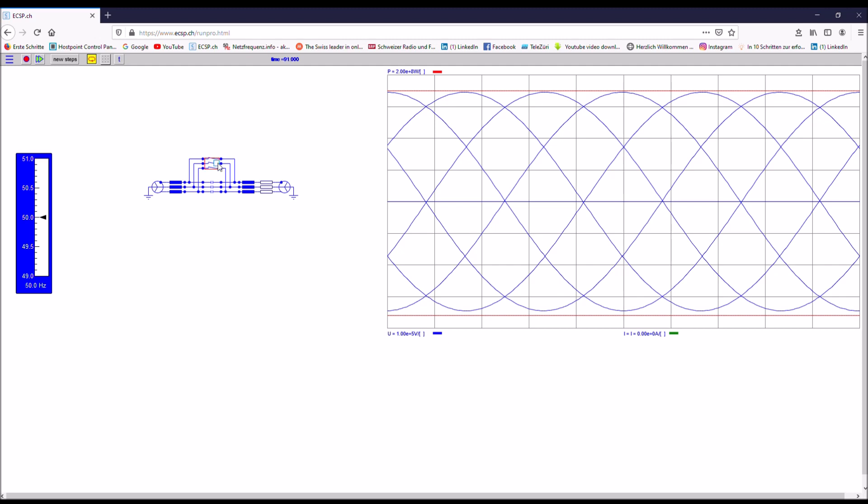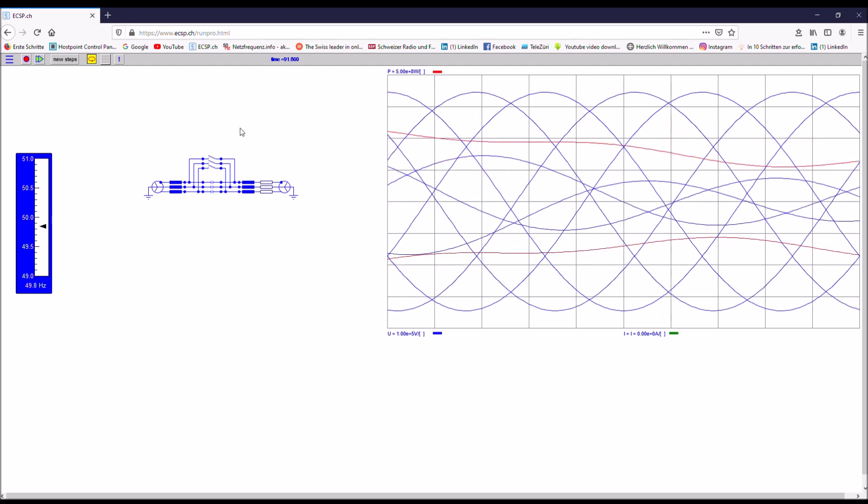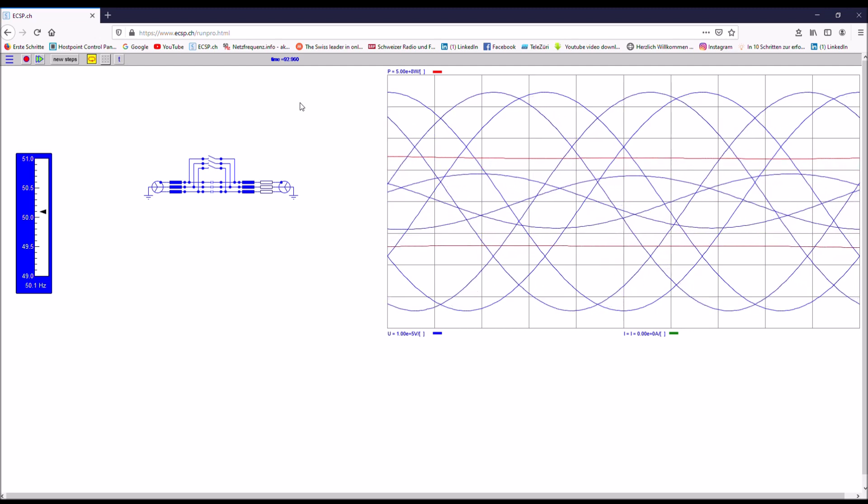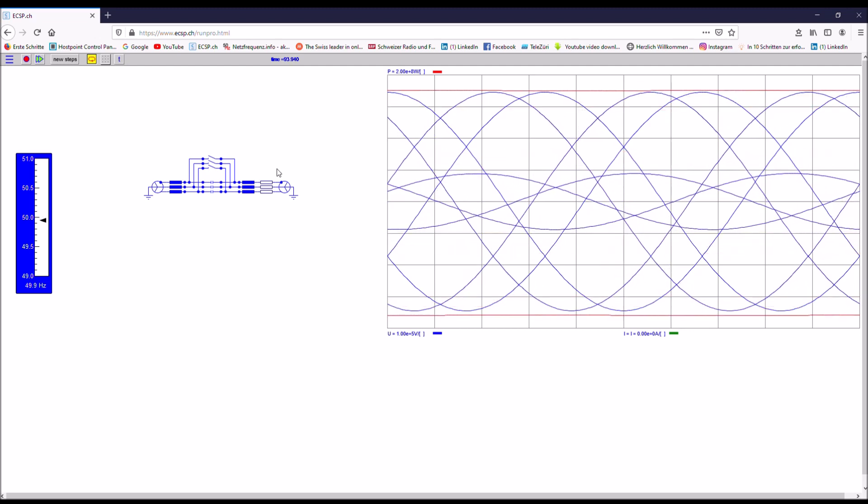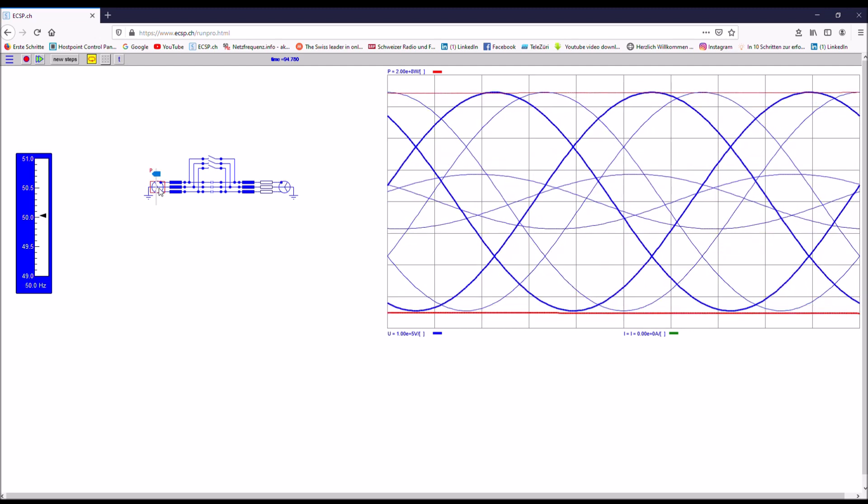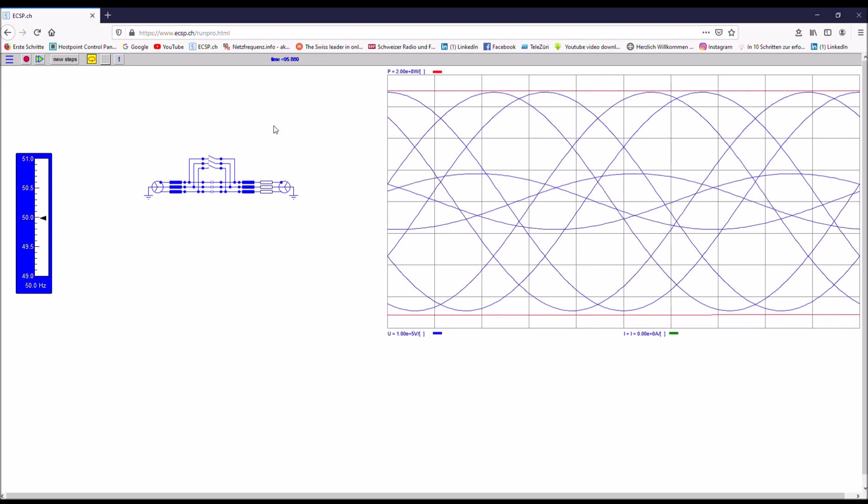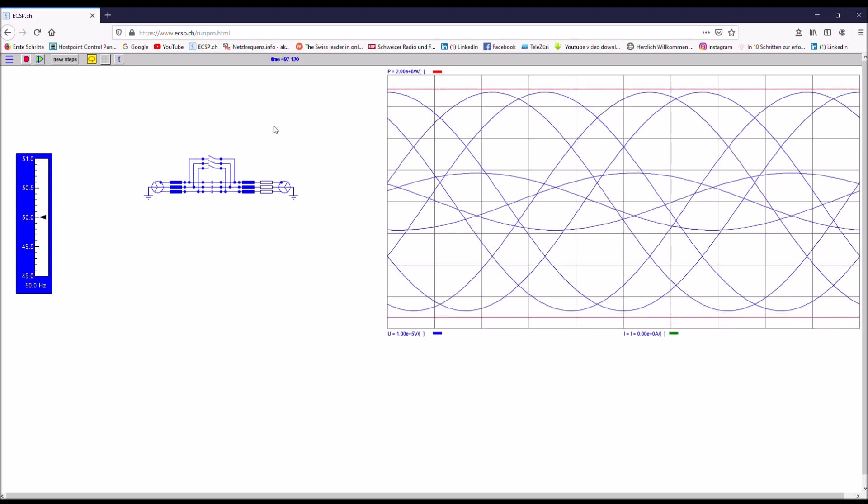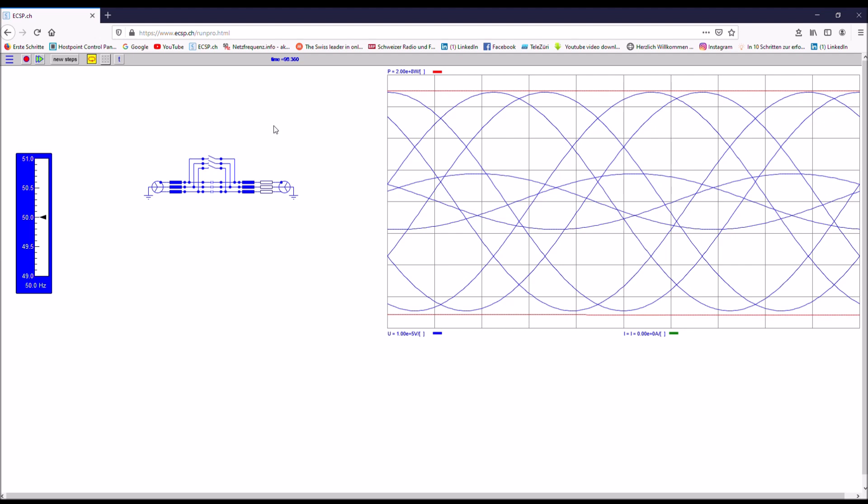And now I switch in the capacitor. So I open the breaker, and what you can see now is how much this angle between the sending end and the receiving end has been decreased. This is how you basically decrease the apparent length of a line by introducing a series capacitor.